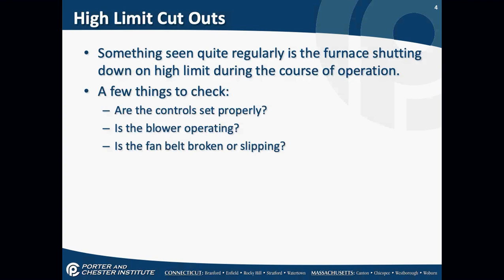You have to check if the controls are set properly. Is the blower actually operating? Is the fan belt broken or slipping? There's two other things to check. If your furnace is going off on high limit, what are the two other things that are important to check? Anybody? What two things do you check if a furnace is going off on high limit?